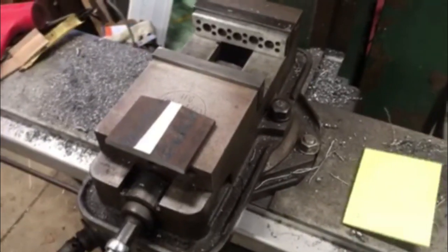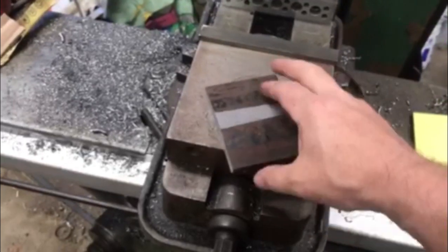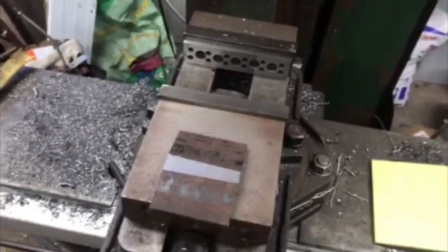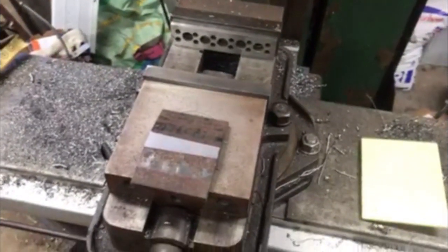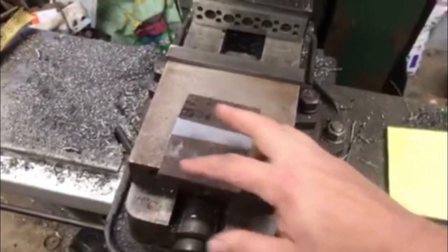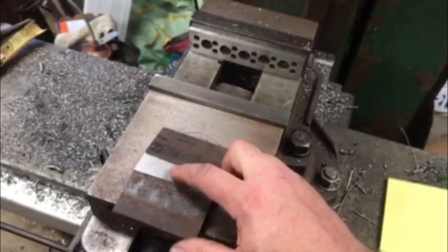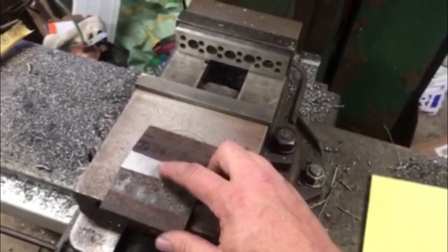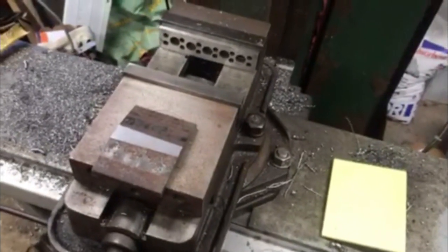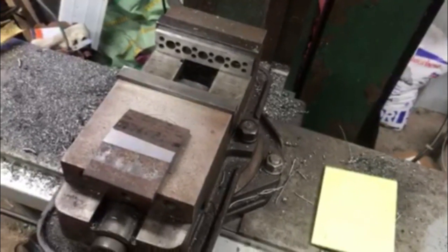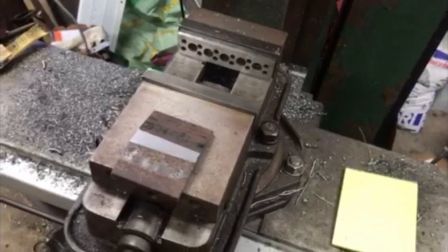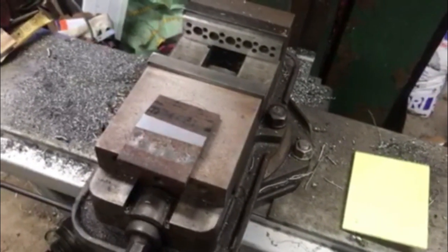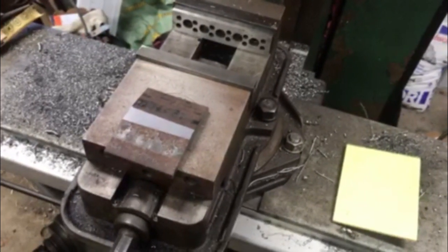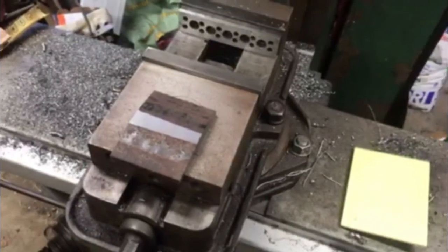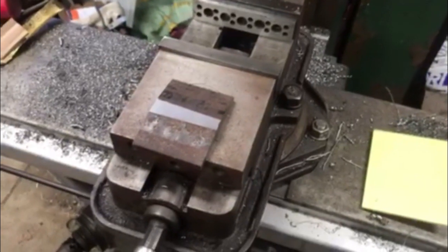So what we're going to do right now is make a plate to bolt over one of the flanges where the pump goes on the line. I'm going to drill 2 bolt holes in it, and drill and tap 1 pipe thread hole here in the middle, so I can put air pressure into the lines and see if I can hear where the leak is down in the cellar. I'm not sure if I'll be able to hear it through the corrugated casing or not, but if I can't find anything in the cellar, that should isolate the leak to somewhere in the lines underground. So we'll get started on this — it shouldn't take much.